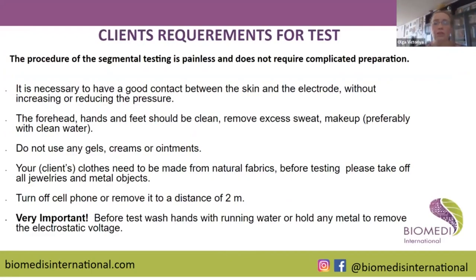The procedure of the segmental testing is painless, and it does not require any complicated preparation for the operator. So what is important? It is important to have very good contact between the skin and electrodes for the device to work properly, without increasing pressure. It just needs to be tied up nicely. The forehead, hands, and feet should be clean. Remove any excess sweat or makeup, preferably with just clean water, no chemical soaps, okay?